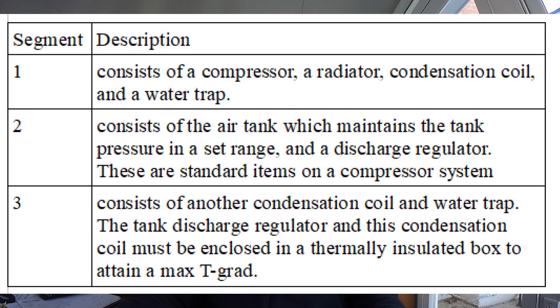The first segment consists of a compressor, a radiator, condensation coil, and a water trap. Segment two consists of the air tank which maintains the tank pressure in a set range and a discharge regulator — these are standard items on a compressor system. And segment three consists of another condensation coil and water trap. The tank discharge regulator and this condensation coil must be enclosed in a thermally insulated box to attain and maintain a max temperature gradient. So let's look at a schematic of such a system.